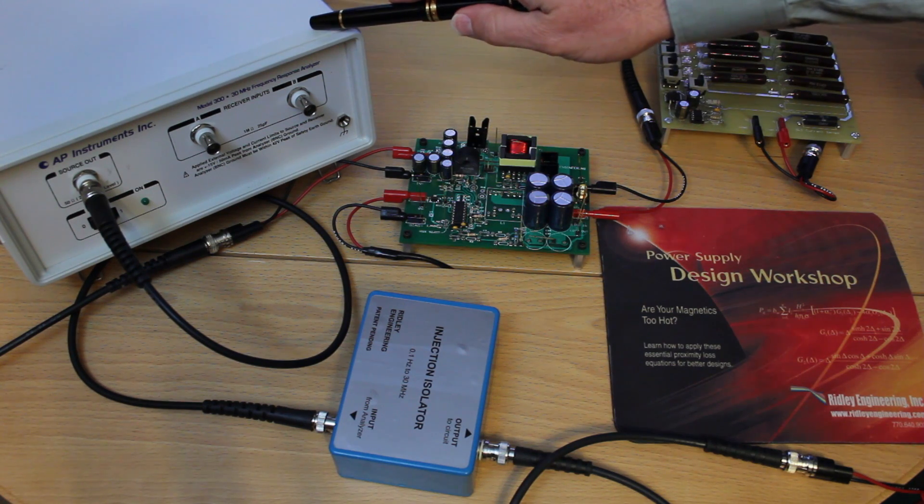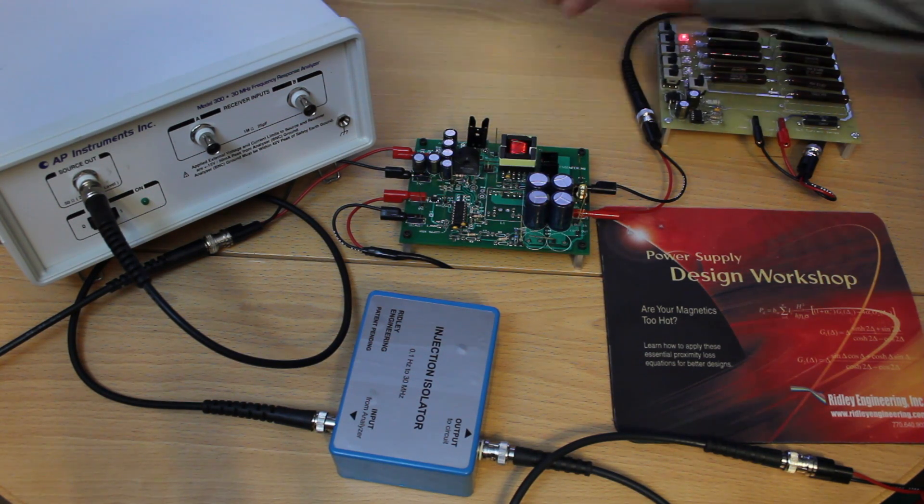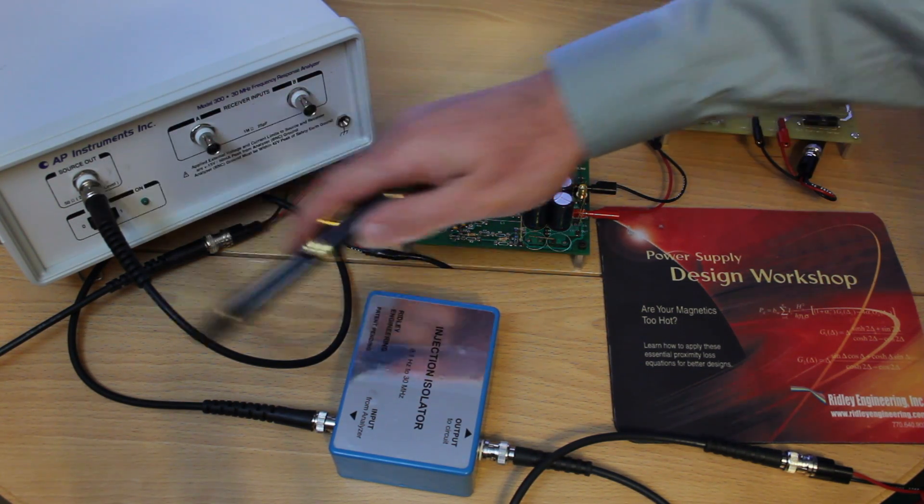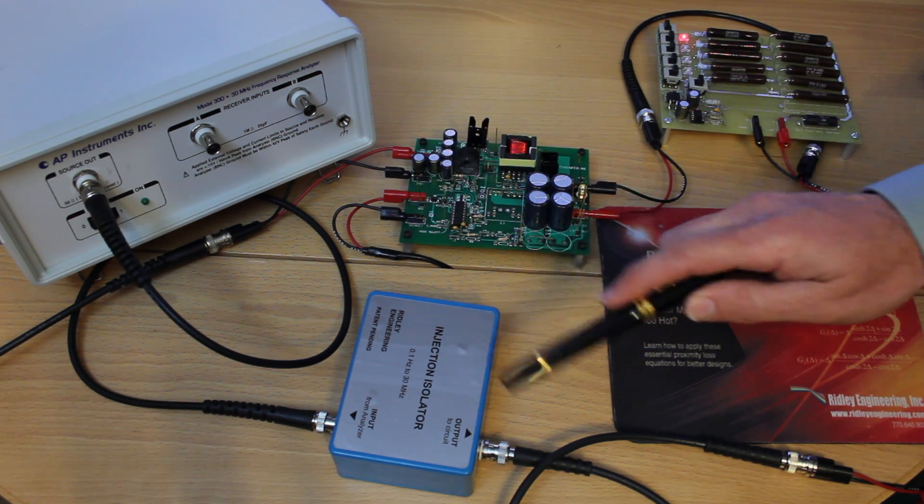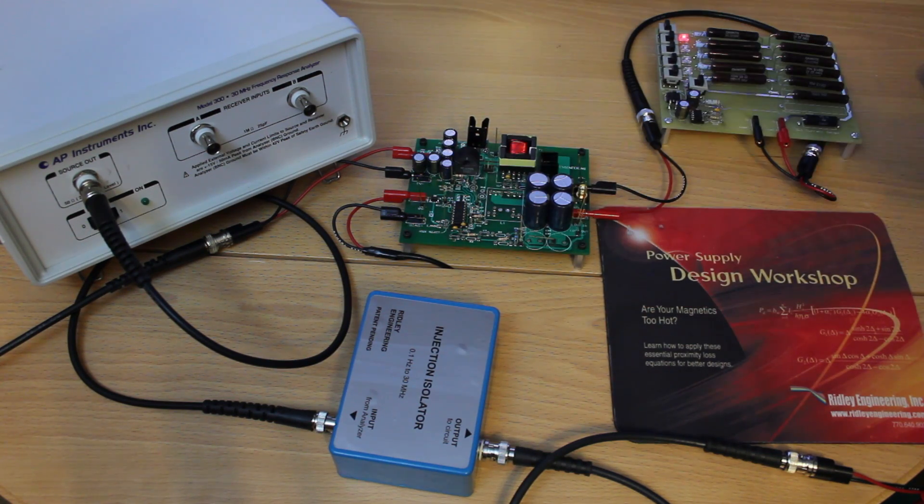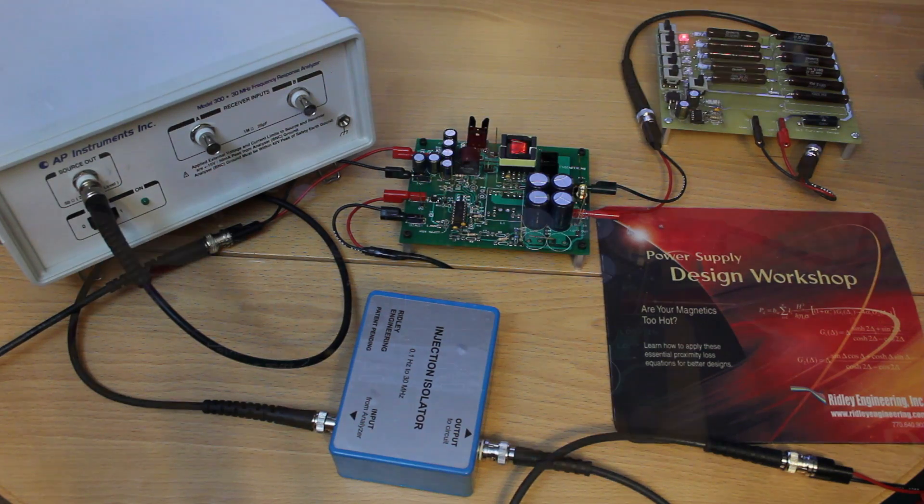Here we have our AP300 frequency response analyzer. The source output comes from here and goes into this extremely wide band injection isolator, which is transformer isolated and works from 0.1 Hertz to 30 megahertz. Now we're going to take the signal from this injection isolator and apply it across the loop resistor in our switching power supply.